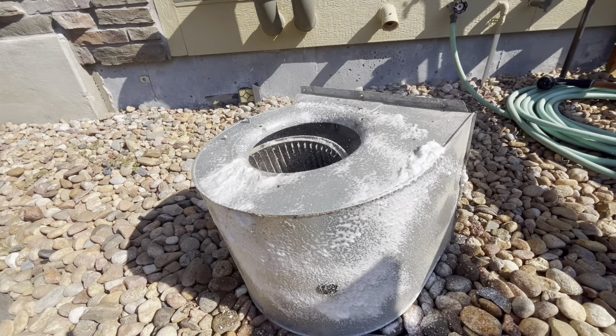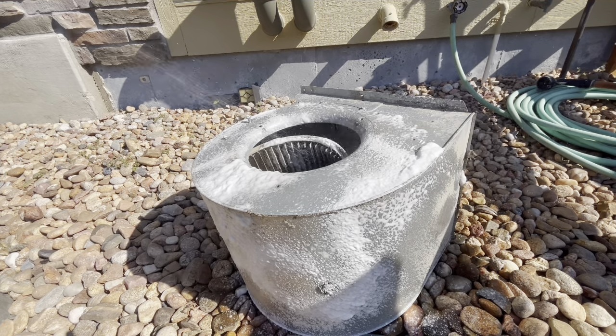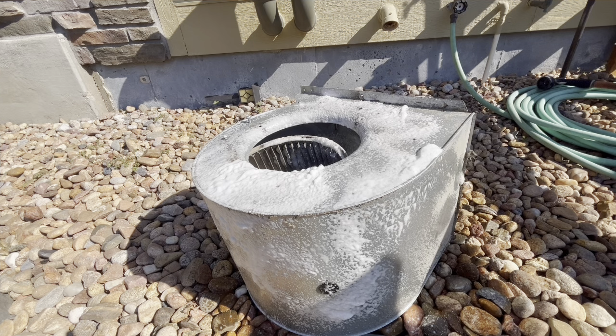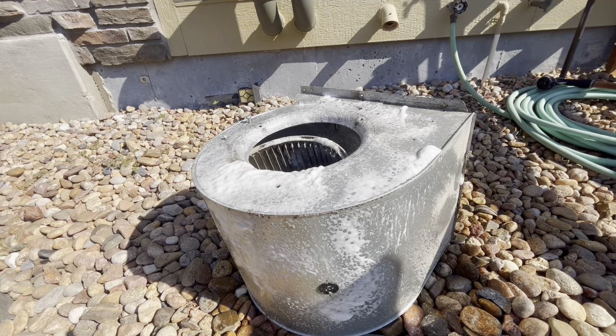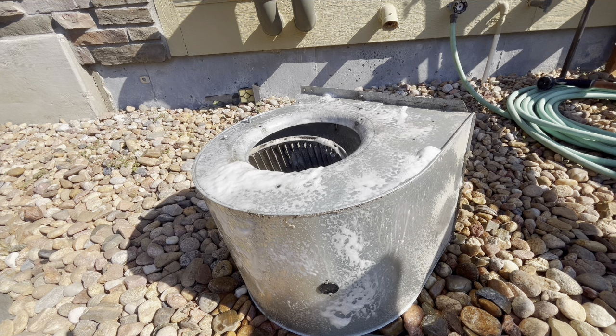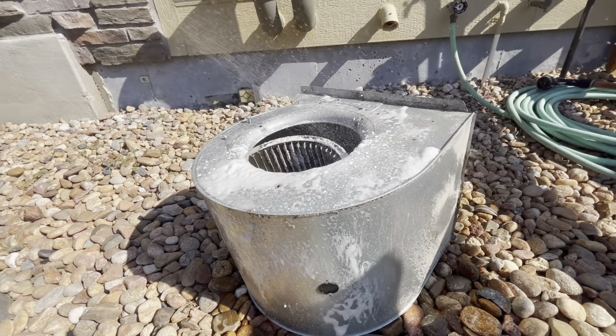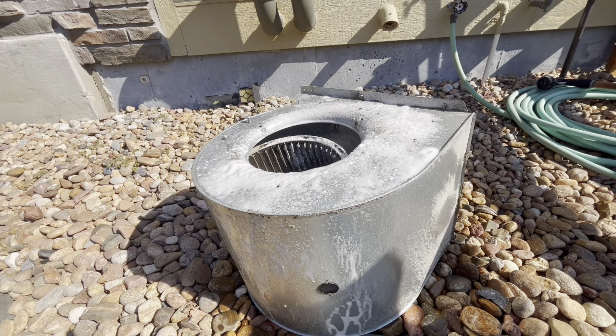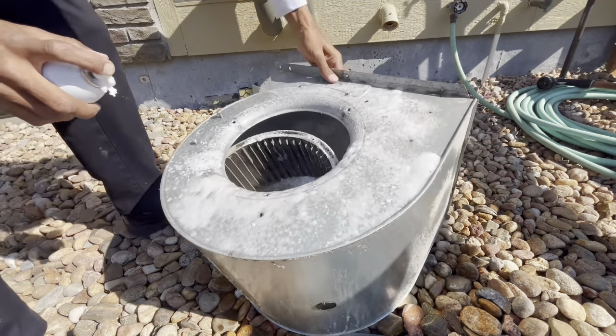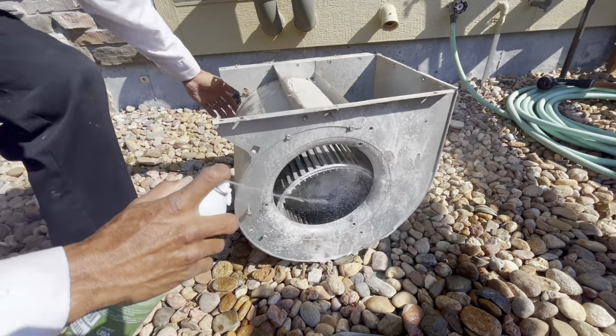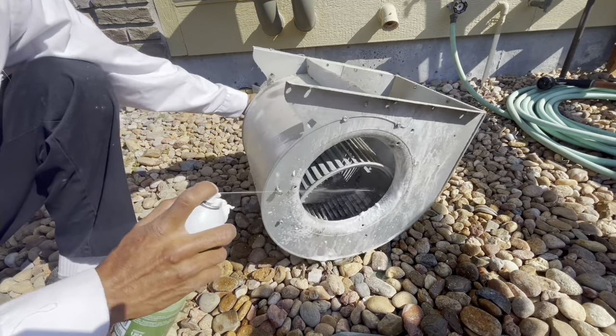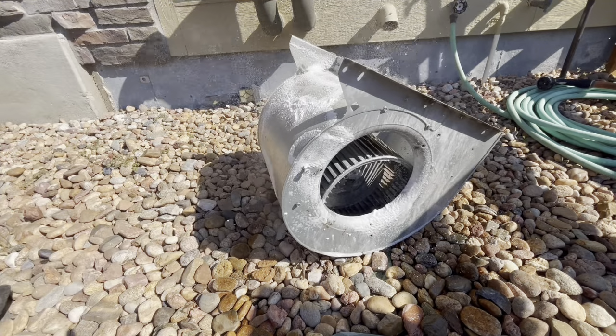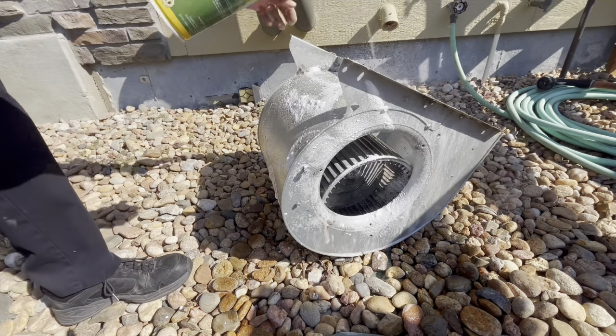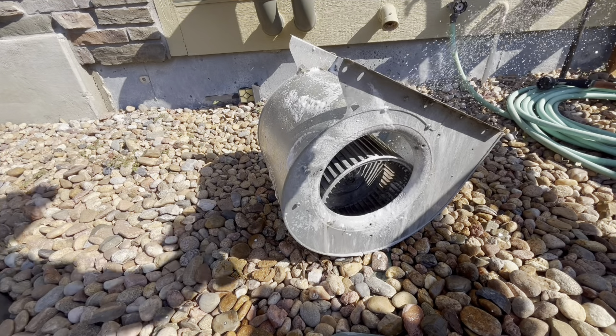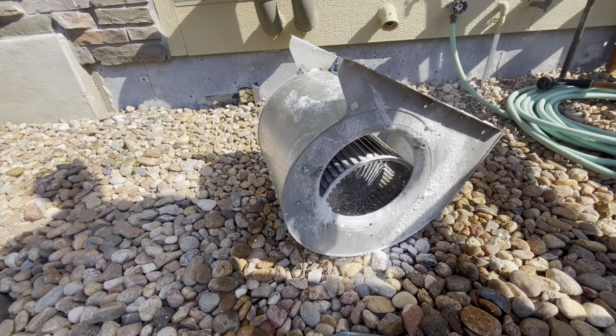For this part, I've taken the blower housing out with the blower wheel and taken it outside, and I'm coating it down with that foam rinse spray, and that's going to break up all that dirt and debris on it. You'd be surprised, once that blower wheel gets, they say, a 20th of an inch of dirt on the wheel, it will throw the airflow off, it'll throw the balance of the wheel off, and it'll make the system work harder, using more electricity. So just by having this simple clean and check done, it will make the system last longer and prevent breakdowns in the future.